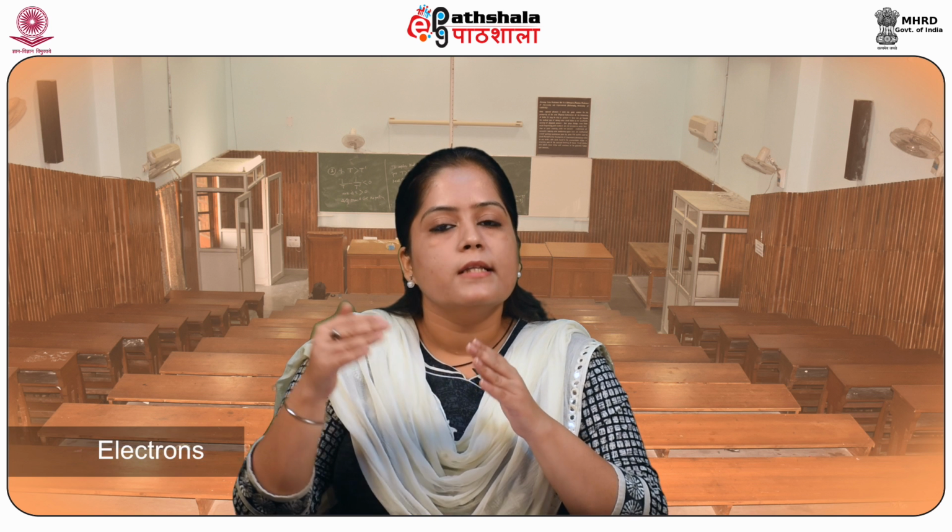Overview of STM. An extremely fine conducting probe is held at about an atom's diameter from the sample. So electrons tunnel between the surface and the tip, producing an electrical signal. While it slowly scans over the surface, the tip is raised and lowered in order to keep the signal constant and maintain the distance. So this enables it to follow even the smallest details of the surface it is scanning.